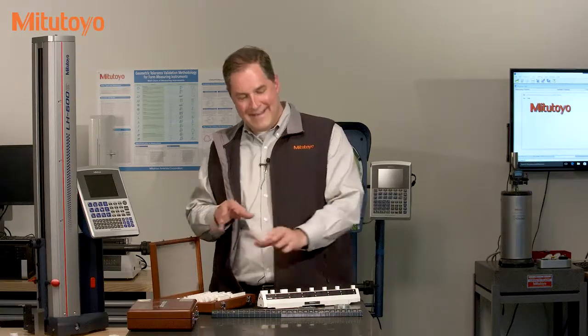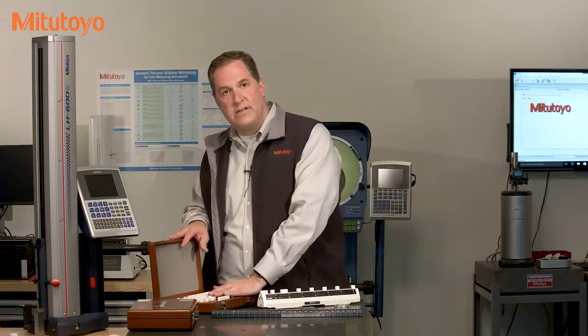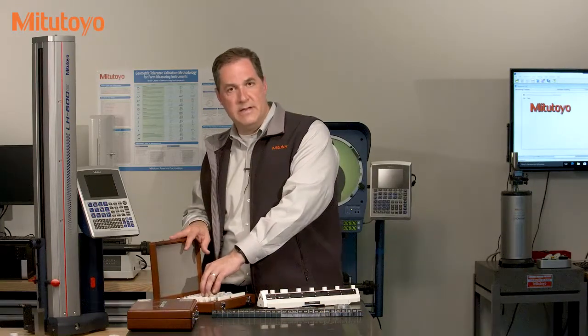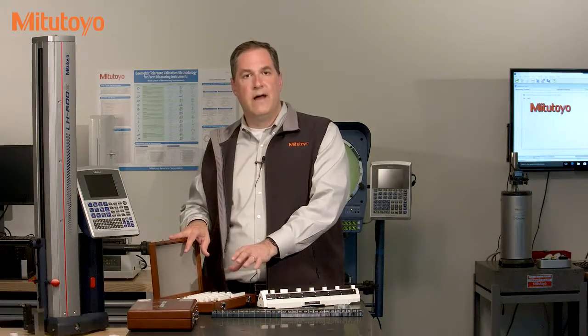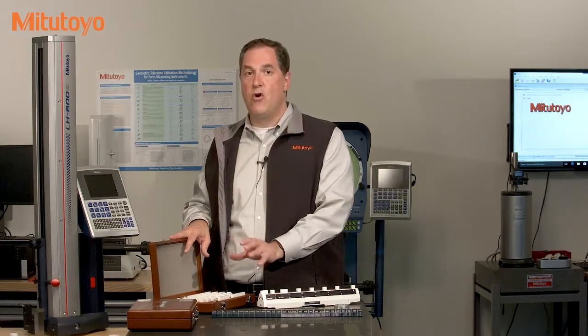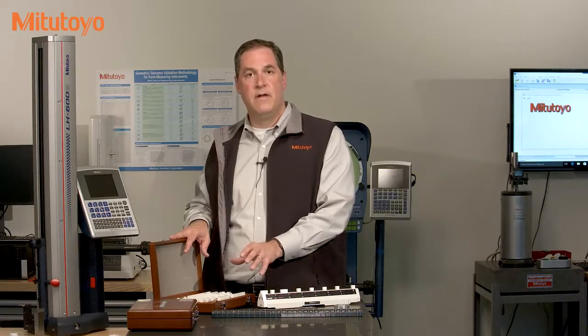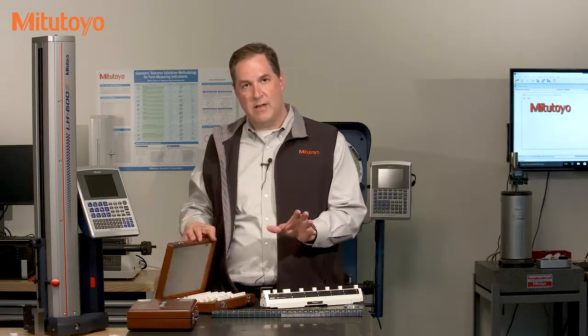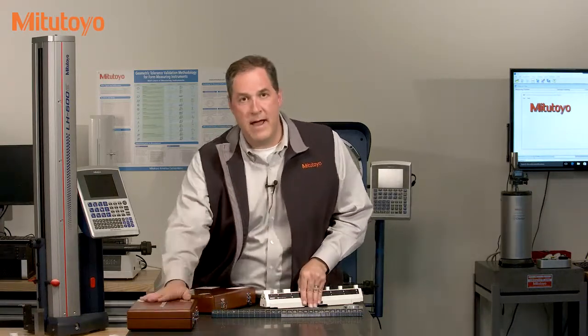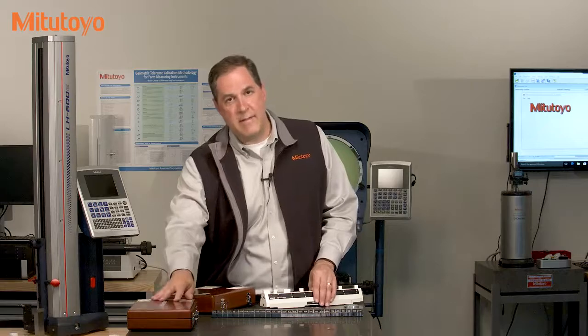The company that owns the caliper doesn't send their caliper checker to NIST. The local calibration lab doesn't send their gauge blocks to NIST. The reason for that is simple. They don't need that level of accuracy, and they sure don't want the cost and lengthy turnaround time at NIST. However, here at Mitutoyo America, being a higher level lab, we send our master gauge blocks to NIST. And then internally here, we calibrate what we call our working masters against the NIST calibrated masters. And then the working masters are used daily to calibrate customers' items.